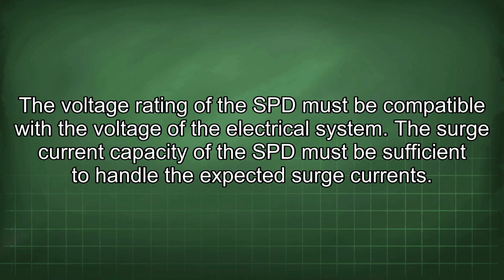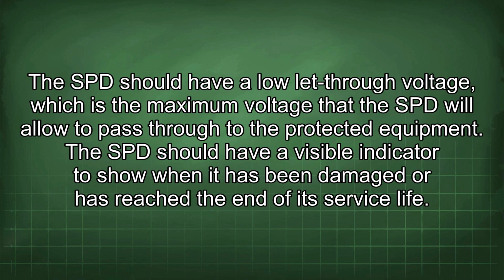The voltage rating of the SPD must be compatible with the voltage of the electrical system. The surge current capacity of the SPD must be sufficient to handle the expected surge currents. The SPD should have a low let-through voltage, which is the maximum voltage that the SPD will allow to pass through to the protected equipment.